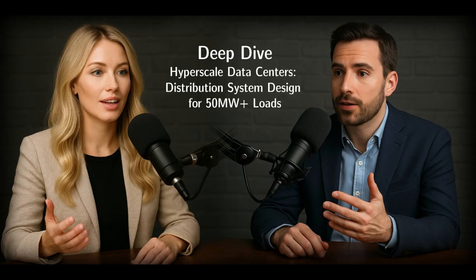Okay. Third, power quality. They need incredibly tight voltage, plus or minus 2%. Our standard distribution systems, we usually design for plus or minus 5%, much looser. Big difference. Huge. And finally, reliability. They often demand 99.99% uptime. Standard distribution might be closer to 99.9%. That extra 9 makes a massive difference in design complexity. So when you put all that together, the load size, the continuous operation, the tight voltage, the extreme reliability, trying to serve that with a bunch of parallel distribution feeders, it really does feel like trying to force something that just doesn't fit, doesn't it?